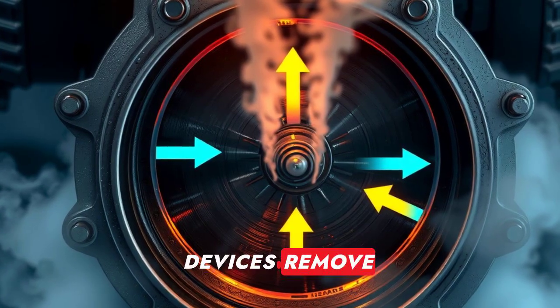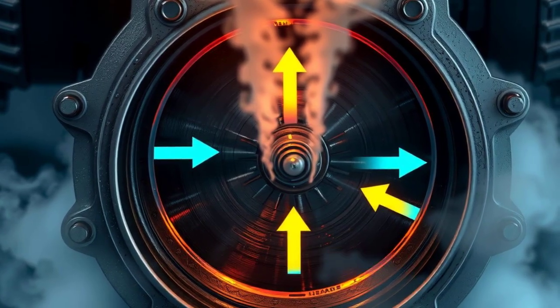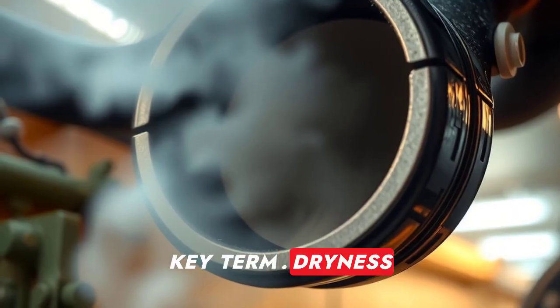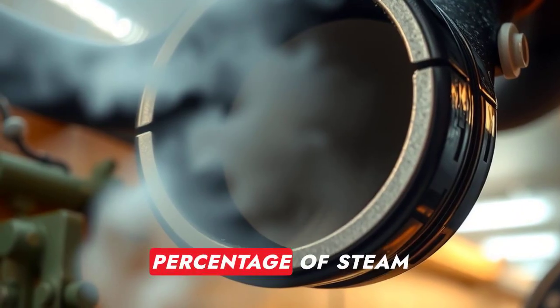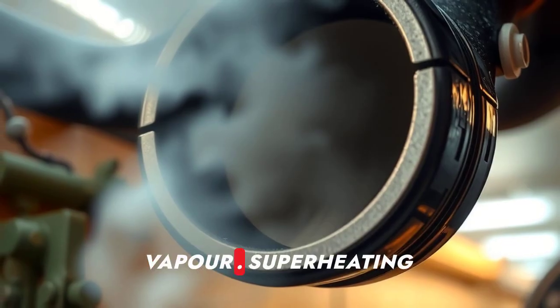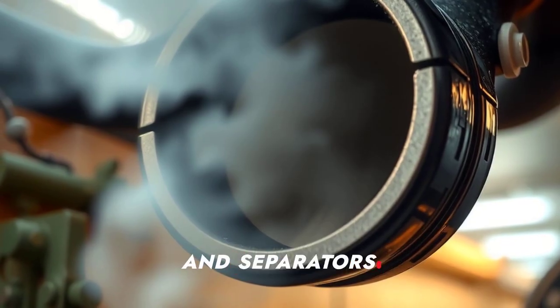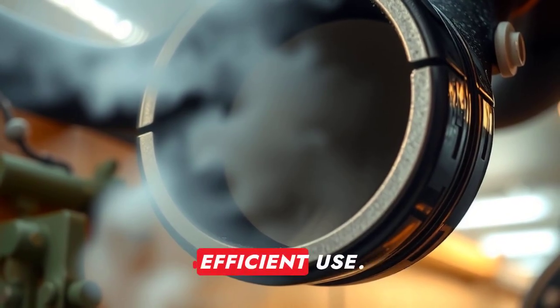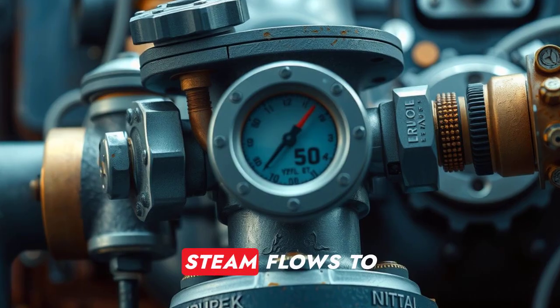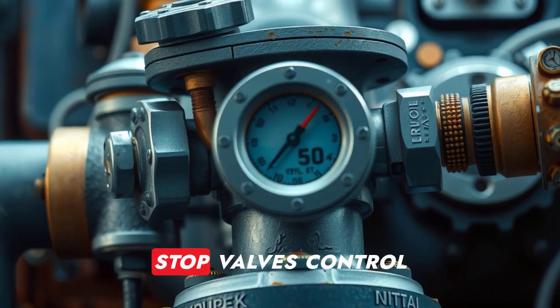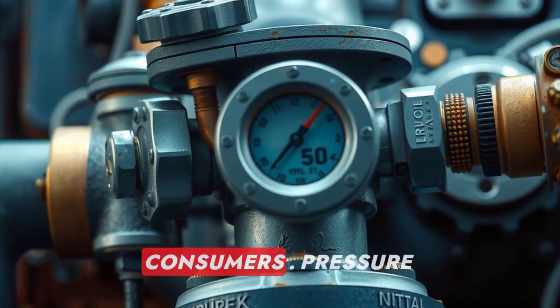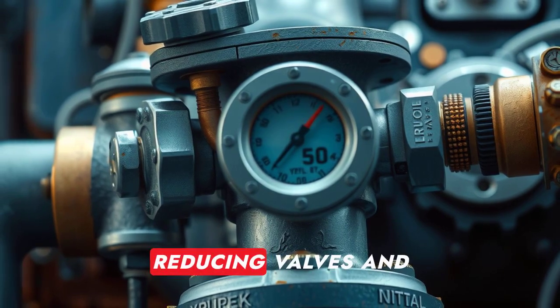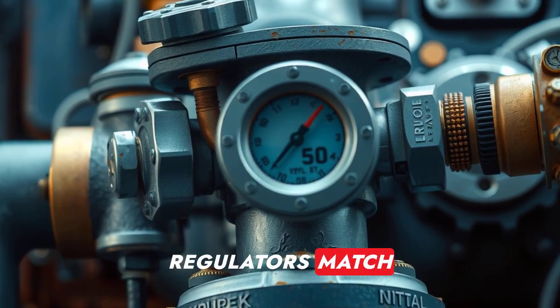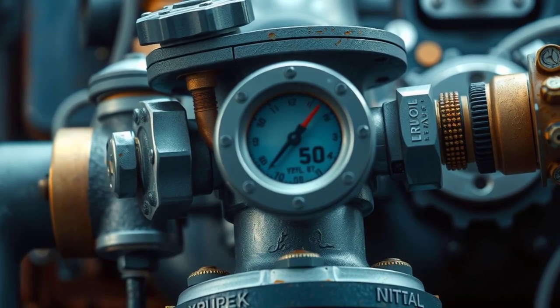Separation devices remove moisture from steam. Key term, dryness fraction: the percentage of steam that is dry vapor. Superheating and separators improve dryness for efficient use. Steam flows to the header where stop valves control supply to consumers. Pressure-reducing valves and regulators match steam to demand.